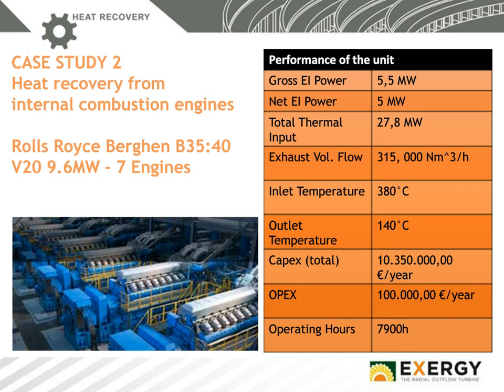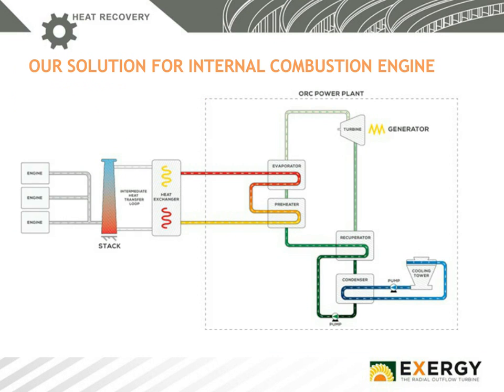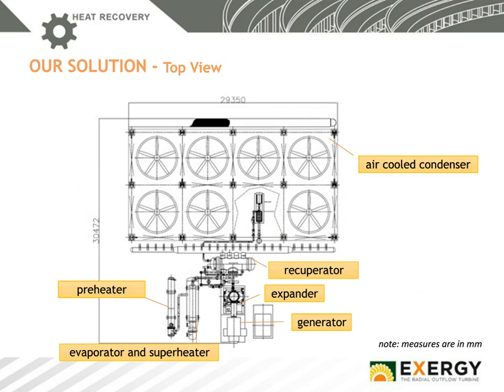If we look at the system, we can see that the flow diagram shows, in this case, the engine groups going to a stack, and before, let's say, the chimney, we have the heat exchanger, and then the system is exactly as Anthony has described before. In this particular case, we would like to use an air-cooled system. The air-cooled system makes the ORC even more automatic, let's say more independent from all the rest of the plant. And it's really a standalone module working beside the power production unit.